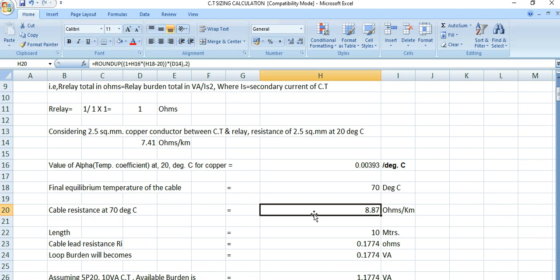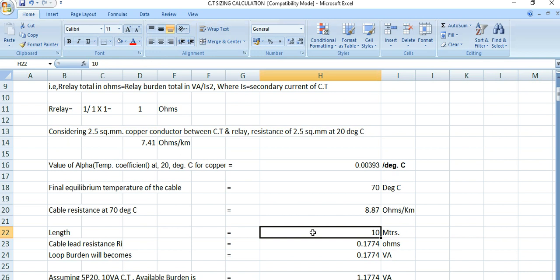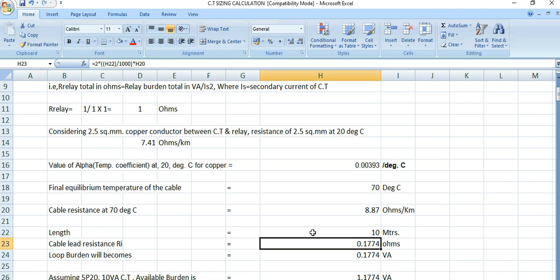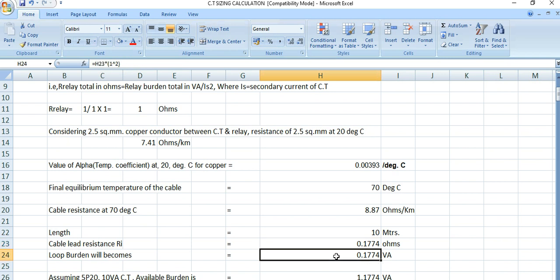The assumed length between the CT and relay is 10 meters. The cable loop resistance is calculated as 2 × (length in meters / 1000) × 8.87, giving 0.1774 ohms. Since the CT secondary current is 1 ampere, the loop burden is also 0.1774 VA.